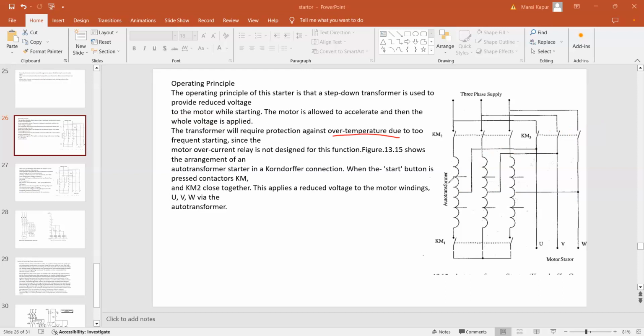You must have seen some engine room blowers. Some engine room blowers are supplied from an auto transformer, and it is written on the panel itself: do not start consecutively 3 times. Or sometimes it is written, after every attempt wait for 15 minutes, right? Because they need some time for cooling if you are starting frequently. The motor overload relay is not designed for this function; motor overload relay is something else, and it is in the starter.